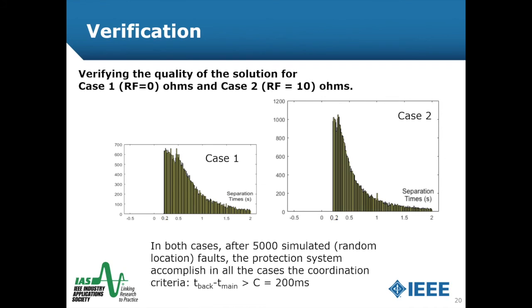Finally, we performed a verification to validate the sensitivity of the optimization solution for both cases. After 5,000 simulations randomly conducted using Monte Carlo programming, we were able to satisfy the coordination criteria with 100% selectivity.